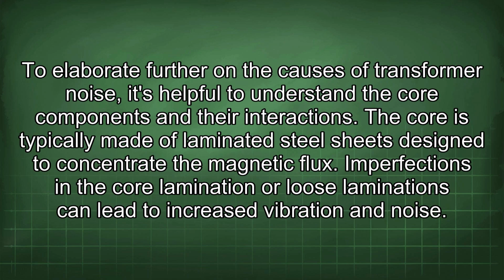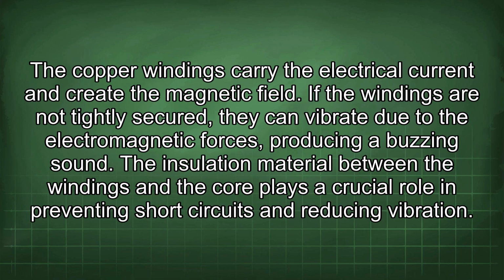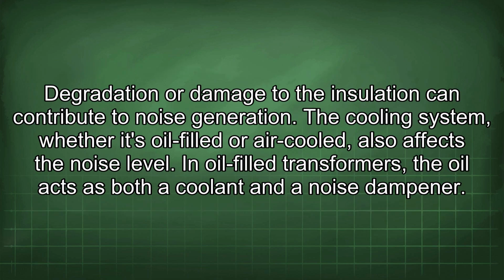To elaborate further on the causes of transformer noise, it's helpful to understand the core components and their interactions. The core is typically made of laminated steel sheets designed to concentrate the magnetic flux. Imperfections in the core lamination or loose laminations can lead to increased vibration and noise. The copper windings carry the electrical current and create the magnetic field. If the windings are not tightly secured, they can vibrate due to the electromagnetic forces, producing a buzzing sound. The insulation material between the windings and the core plays a crucial role in preventing short circuits and reducing vibration. Degradation or damage to the insulation can contribute to noise generation.